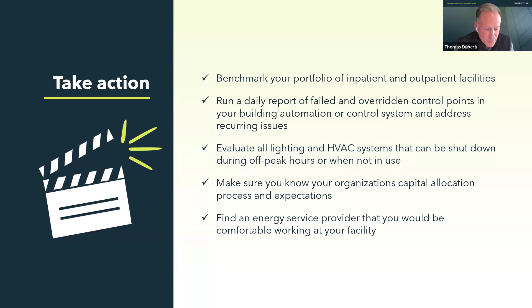If you're new to this, let me break this down. Every commercial building is obligated to ventilate, and there are standards established for CO2 levels within those buildings. Hospitals and medical facilities have higher standards than other buildings for obvious reasons. But many systems default to ventilating way more than needed, particularly when a building goes through periods of reduced occupancy yet is still being ventilated at a very significant rate. You might ask, what's the big deal about bringing in more outside air? The big deal is that outside air coming in is often really hot and/or humid, or really cold, meaning it needs to be cooled or heated. So reducing the amount of air flowing into a building can dramatically affect the cost of HVAC.